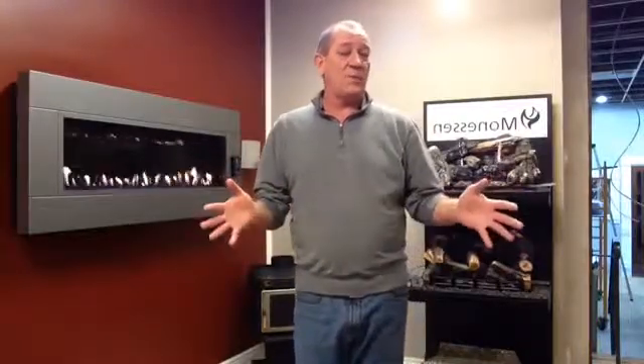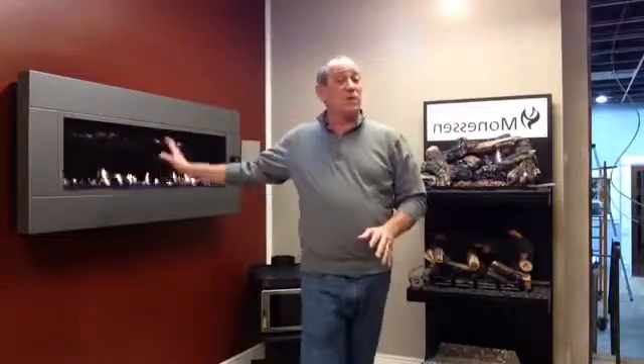Now, that brings us down to anywhere in the home. Bathrooms and bedrooms, most generally you do not want to put vent-free in. And it's not that it's unsafe, it's that you need to know the rules again. The amount of BTUs that are produced by these, like this set here's 33,000 BTUs. I can't put something 33,000 BTUs into a 10 square foot bathroom, or into a small bathroom, or into a smaller bedroom. But if we lower down the BTUs, we could go up to 6,000 in a bathroom, we could go up to 10,000 in a bedroom. Now, these are rules, and I'm pretty sure about those numbers, but always double check before you decide to try to put something into a bedroom or a bathroom. Into the main home, with a large amount of square footage and a lot of oxygen, then you should have no problems burning vent-free.